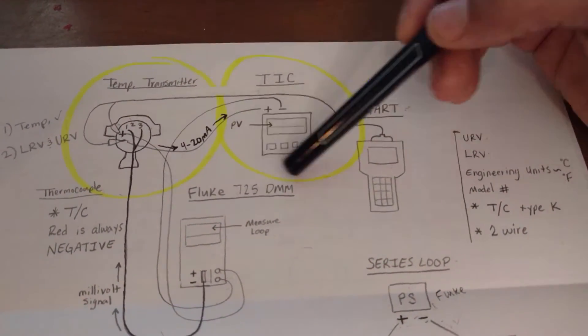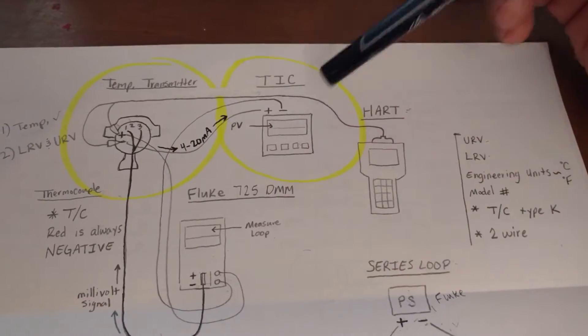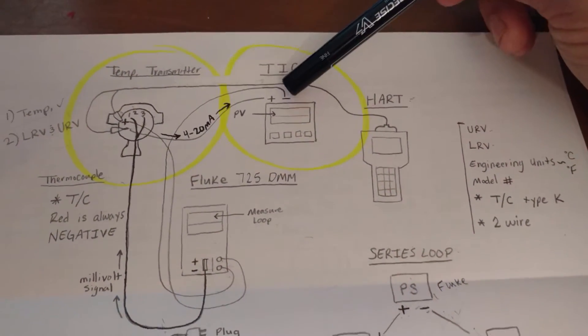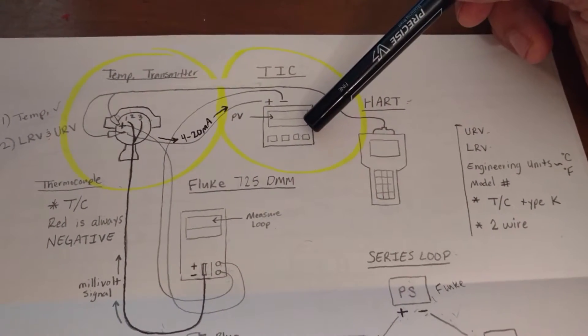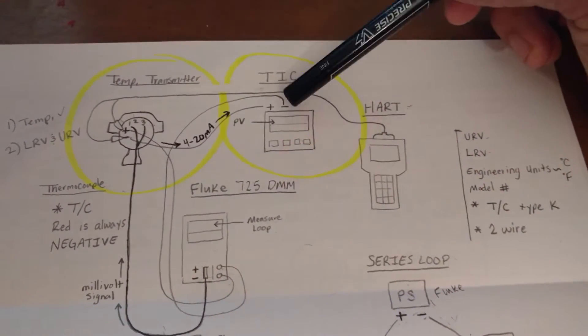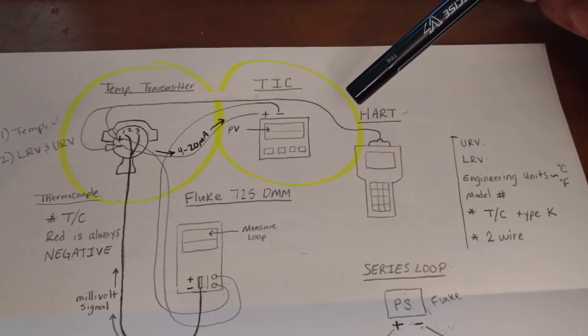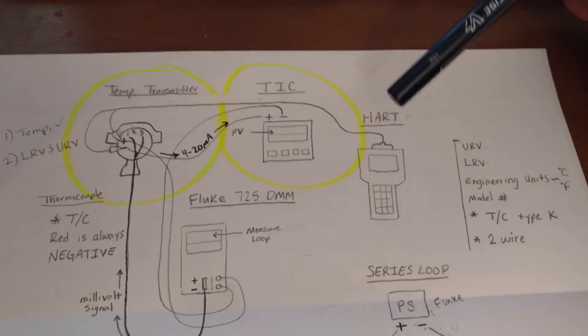And this device is going to have an upper range value and a lower range value programmed as well. And it's going to be able to display some type of a value that's based on this 4 to 20 milliamp signal and its upper and lower range values.